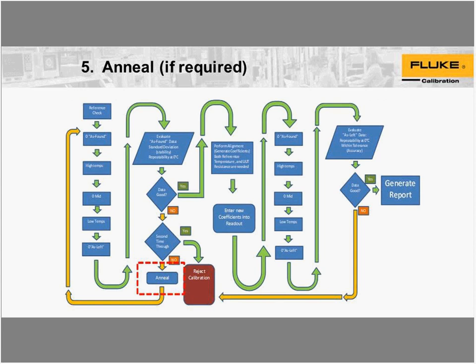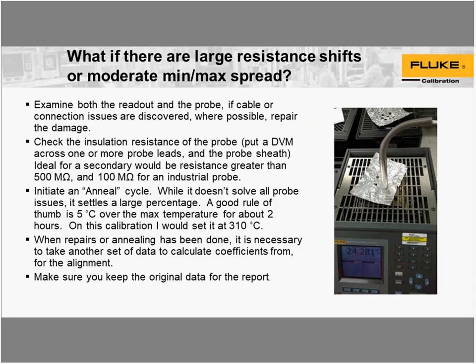Annealing is putting your probe back into an oven or a dry well. Set it to your max temperature plus 10 degrees for about 2 to 3 hours. Then you let it cool back down, and then you go ahead and start the process all over again. Don't erase your original as-found data. You'll just need to take an additional set so that you can get new resistance readings and get a good set of coefficients.